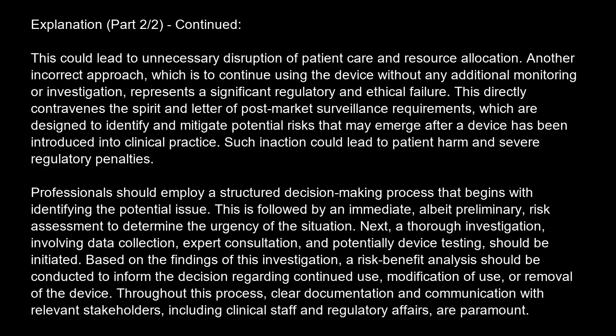Professionals should employ a structured decision-making process that begins with identifying the potential issue. This is followed by an immediate, albeit preliminary, risk assessment to determine the urgency of the situation. Next, a thorough investigation involving data collection, expert consultation, and potentially device testing should be initiated. Based on the findings of this investigation, a risk-benefit analysis should be conducted to inform the decision regarding continued use, modification of use, or removal of the device. Throughout this process, clear documentation and communication with relevant stakeholders, including clinical staff and regulatory affairs, are paramount.